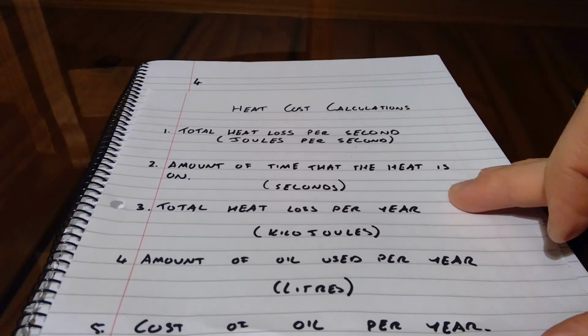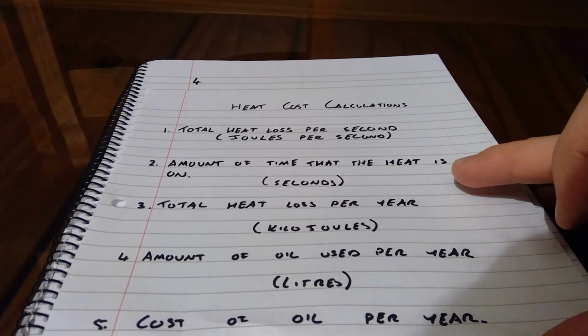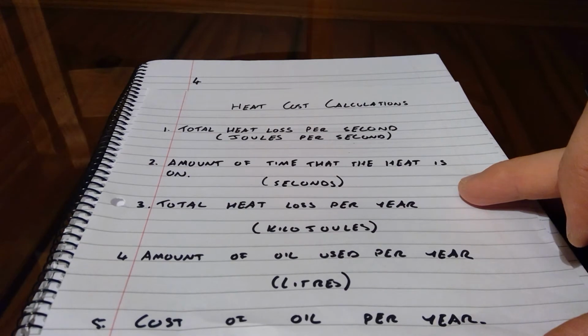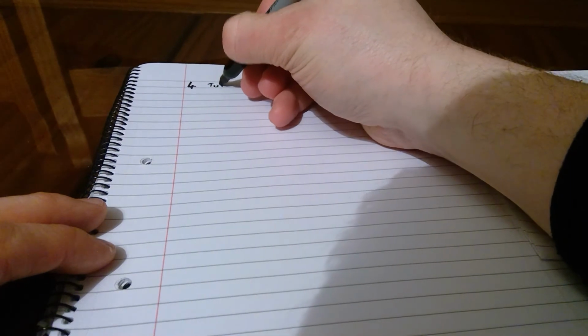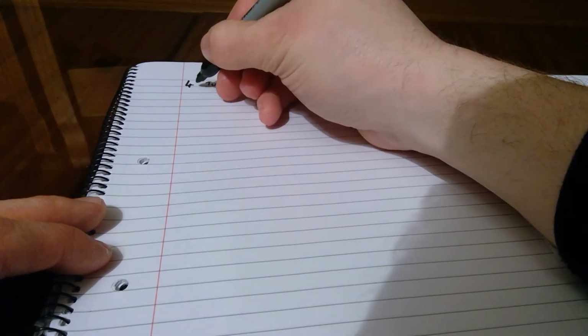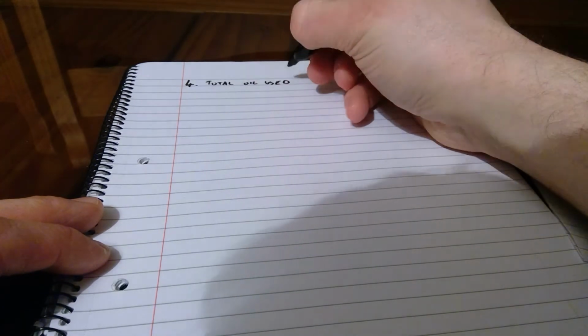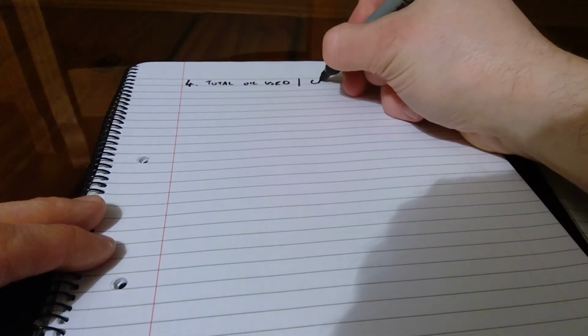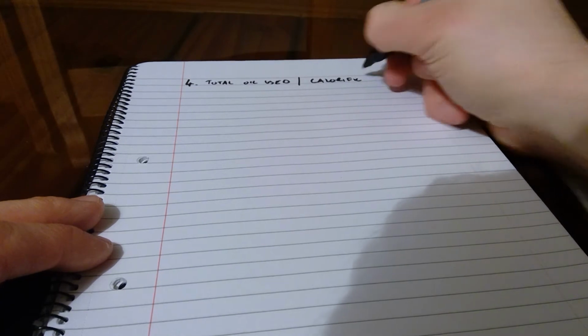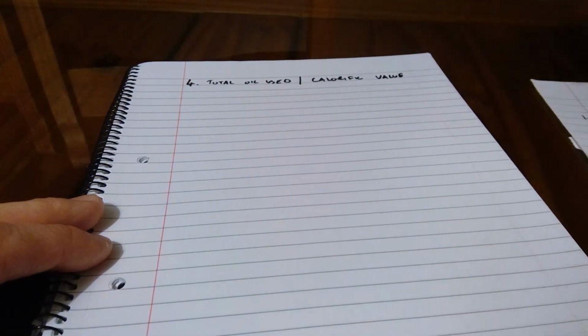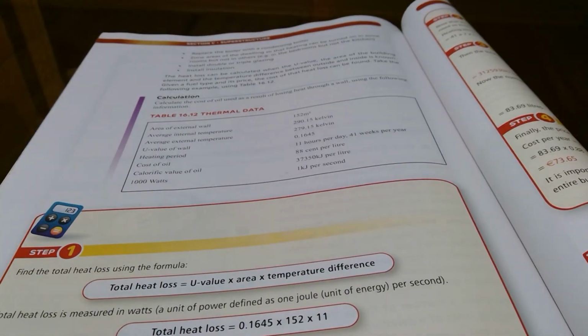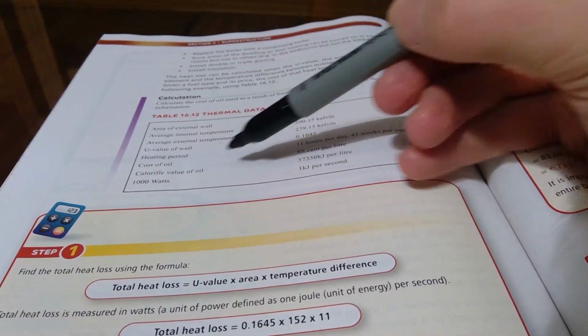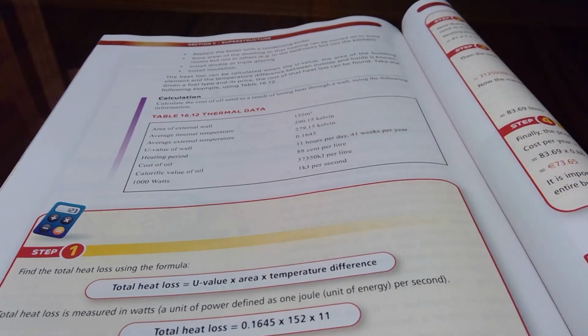Step four, we now need to calculate the amount of oil used per year. So what we need to do for step four is take the total oil used, sorry, divided by the calorific value. Now, the calorific value is a term you may never have heard before. You don't really need to understand it. The calorific value of the oil is basically the quality of the oil. The calorific value is given to us here: it's 37350 kilojoules per litre.